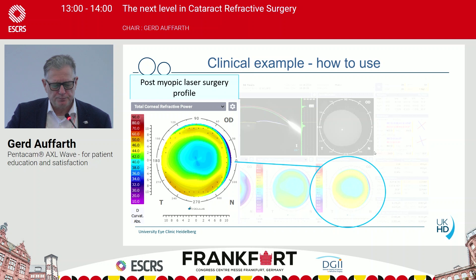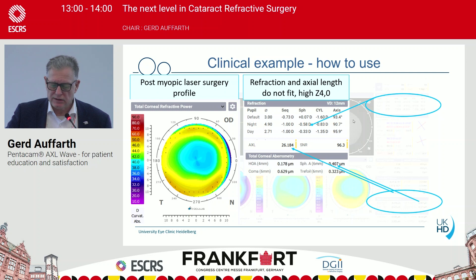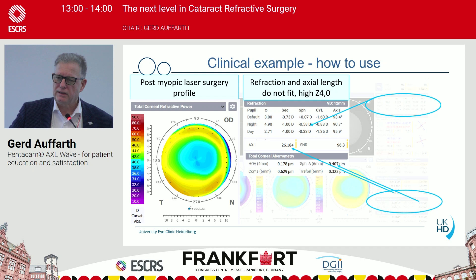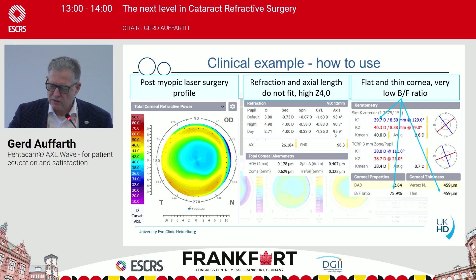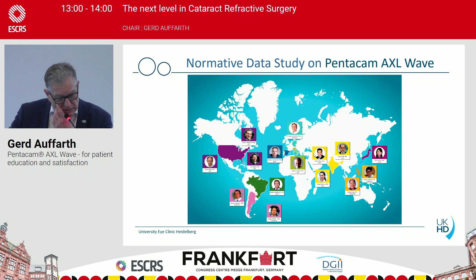Here is a post-myopic laser profile. The machine already realizes this is a long eye but has a normal refraction. The patient doesn't always tell you that. The technician might write down 'laser treatment,' but it could be laser treatment of the cornea or a retinal hole. For the patient, everything you do in the eye is laser surgery, regardless of what you do. But if you look at the machinery, you can see — flat and thin cornea, and the back-front ratio is fairly low, which tells you something has been done with the cornea.